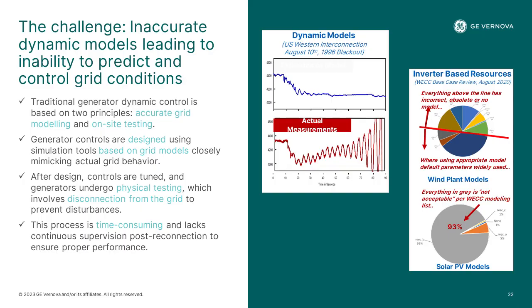So this was the US Western Interconnection 1996 blackout, where the Western Interconnection separated into 4 different regions. Now you're seeing 2 trends here. The trend on the top was what the dynamic models were predicting, the blue trend. The trend below is what was actually measured by fault recorders. And what you can see is a real mismatch here, because the blue trend is showing a stable system, while the red trends are showing growing oscillations, which resulted in the system, again, separating into 4 different regions.